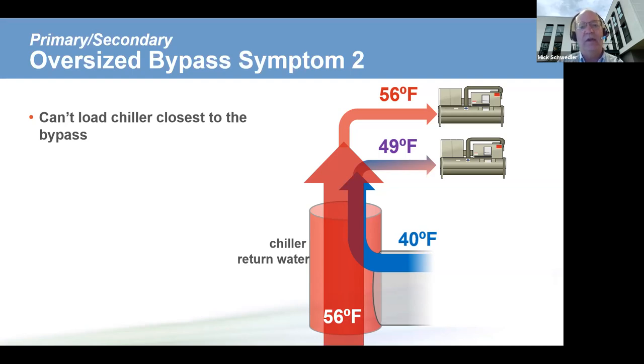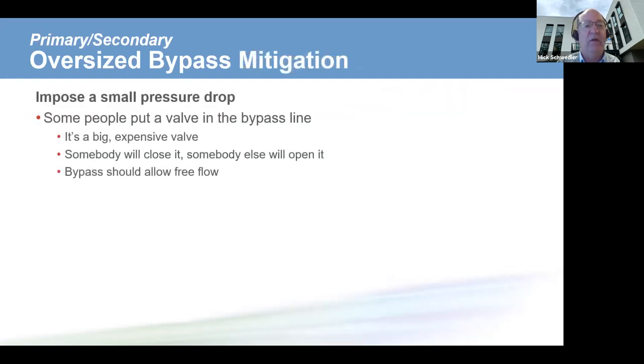So if you are looking at a system and you see things like this, the first place to look is generally, is the bypass line the right size? Well, what happens if it isn't the right size? Well, the first thing, we'd like to impose a small pressure drop, because we do want water to flow freely in either direction, but we don't want the water to short circuit.